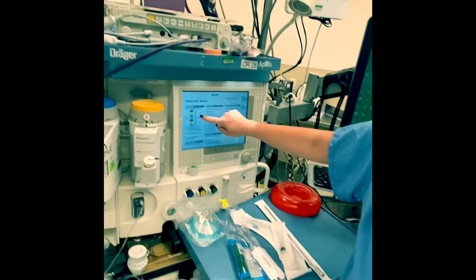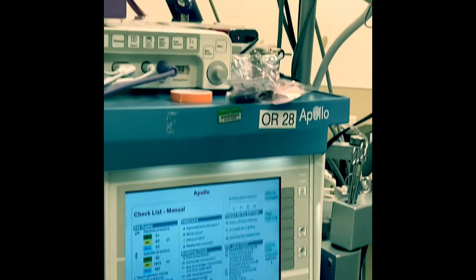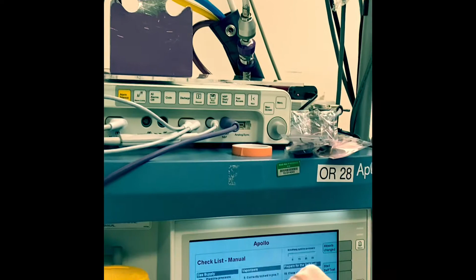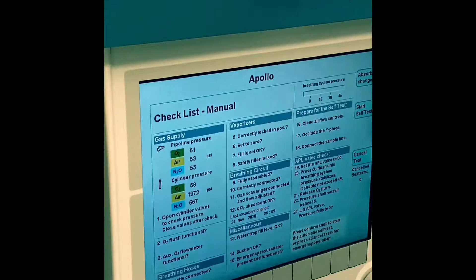Okay, so we'll move back to our machine now that it's turned itself back on. You're going to have your pipeline pressures that you're going to want to check here and make sure they're around 50. The pipeline pressures come from the actual main OR pipeline pressure. We can't do anything about these, but if they're not within 50, call the anesthesia tech and just have it troubleshooted. So then we're going to check our cylinder pressures.